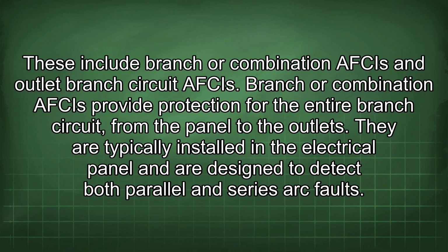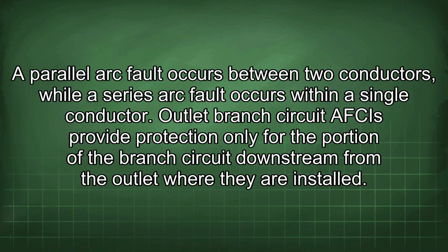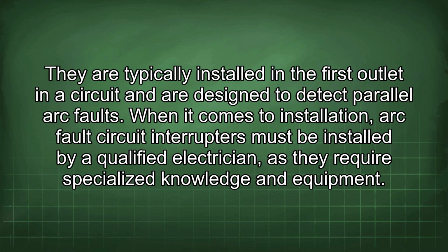Branch or combination AFCIs provide protection for the entire branch circuit from the panel to the outlets. They are typically installed in the electrical panel and are designed to detect both parallel and series arc faults. A parallel arc fault occurs between two conductors, while a series arc fault occurs within a single conductor. Outlet branch circuit AFCIs provide protection only for the portion of the branch circuit downstream from the outlet where they are installed. They are typically installed in the first outlet in a circuit and are designed to detect parallel arc faults. When it comes to installation, arc fault circuit interrupters must be installed by a qualified electrician, as they require specialized knowledge and equipment.